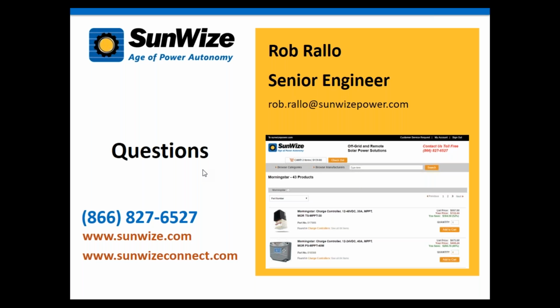So that would be the only maintenance I would see, and you want to catch that before it's been compromised, because once that's compromised and the corrosion gets in there, then the module is going to fail, and there's really not much you can do other than replace it. But again, there should not be any maintenance unless you notice there's some type of scratch or scrape or something that has damaged that back skin, that Tedlar, and then seal whatever that scratch or gash is with a high grade silicone.